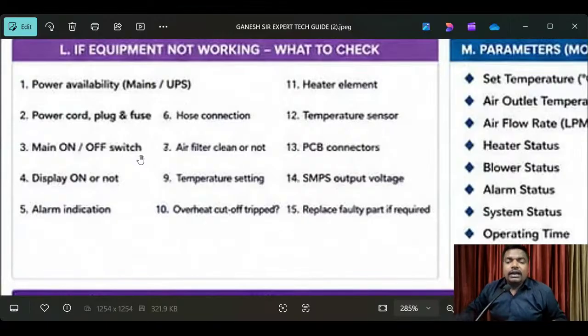And alarm indications, see here, alarm indications are also very, very important, so don't keep them muted. As per medical norms, we should not keep any alarms muted, because alarms are very important to alert the patient, doctor and engineer. Whenever we get a complaint, we have to be alert, because sometimes high temperature can occur and the patient may even get burned. Many things can happen. That's why alarm high limit, low limit and medium limit are recommended by the manufacturer, based on basic engineering principles in the healthcare sector. That's why we should not tamper with them. If alarms keep sounding, don't ignore them, and don't try to mute the alarm. It is very important to try to provide solutions.